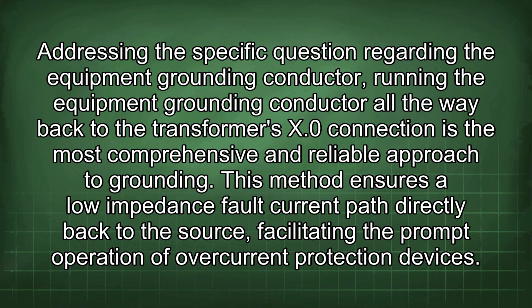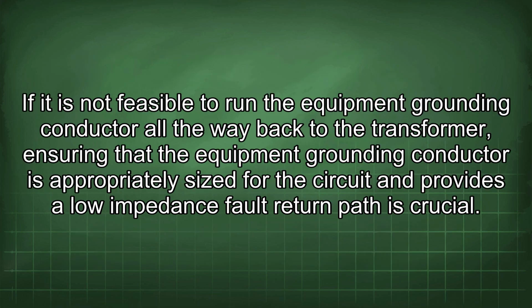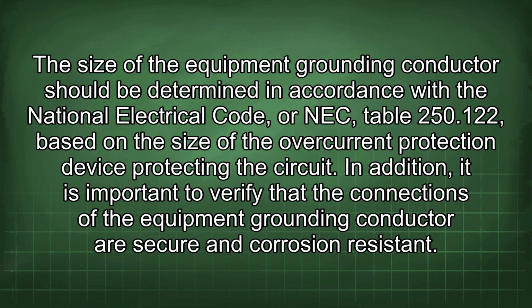Addressing this specific question regarding the equipment grounding conductor, running the equipment grounding conductor all the way back to the transformer's X0 connection is the most comprehensive and reliable approach to grounding. This method ensures a low impedance fault current path directly back to the source, facilitating the prompt operation of overcurrent protection devices. If it is not feasible to run the equipment grounding conductor all the way back to the transformer, ensuring that the equipment grounding conductor is appropriately sized for the circuit and provides a low impedance fault return path is crucial.